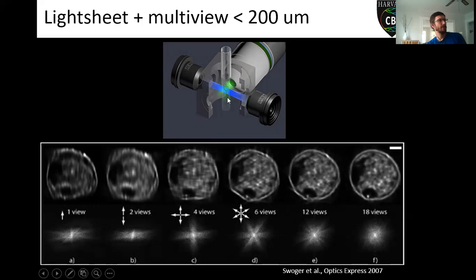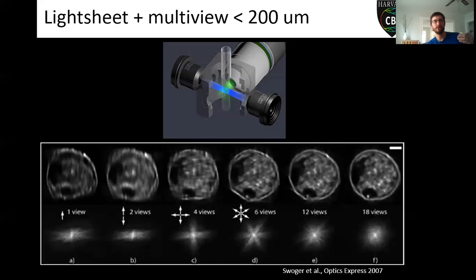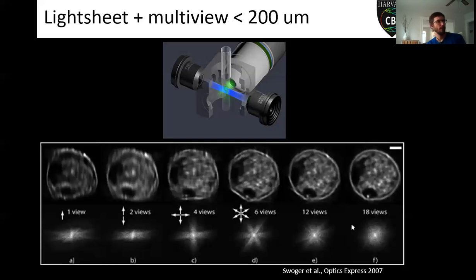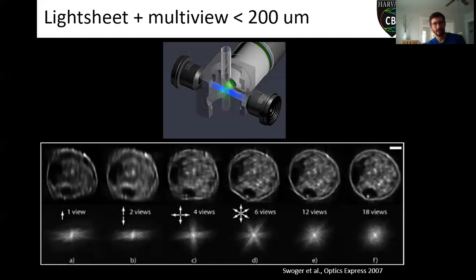By rotating the sample we can image through it from multiple angles and then put all those angles back together again. If my organoid is sitting here and I move it through the light sheet, the side closest to the objective gives a really good image, but that image degrades the deeper I go. If I rotate it 180 degrees, I can now image that previously poor side with really high quality and combine the two views together. It doesn't have to be just two views — we can do multiple views. The more views you do, the better your image becomes. This is the same principle as a CT scanner: the more points you image from around your sample, the better your image gets. This essentially allows us to double our imaging depth, getting up closer to 200 microns.